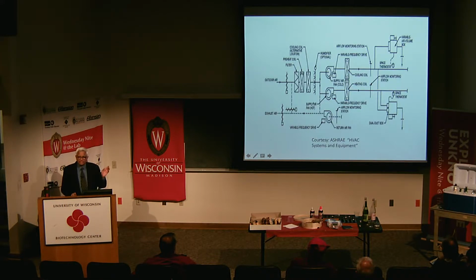I have not even included the chiller equipment and the heating equipment. I have not shown the cooling coil valve nor the heating coil valve. So the fault can occur with the damper, with the set point of the ventilation air, with the outdoor air damper, with the fan, with this fan, or with these boxes, or with the temperature sensors which are here and which are here. So you can have numerous fault scenarios. So the reason I took this was it gives an incentive to look at an automatic fault detection system. This is called a dual fan, dual duct system.